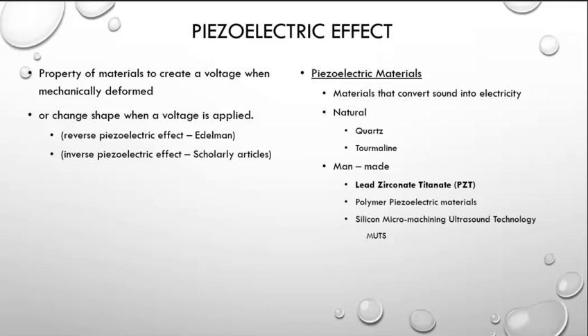Now, modern transducers use polymers that are piezoelectric materials. And there's also a piezoelectric material known as MUTS, which stands for silicon micro-machined ultrasound technology. So the one you need to remember is PZT. Just remember that in addition to PZT, other crystals are made of polymers and more advanced materials.